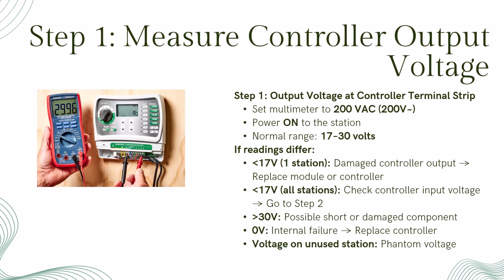Step 1 is to test the output voltage right at the controller terminal strip. Most irrigation controllers operate around 24 volts AC, but in reality, you'll see anywhere from 17 to 30 volts depending on your input voltage. The transformers used in controllers are 5-to-1 step-down transformers that take the incoming line voltage of 120 volts and change it to 24 volts. 120 volts divided by 5 is 24 volts.